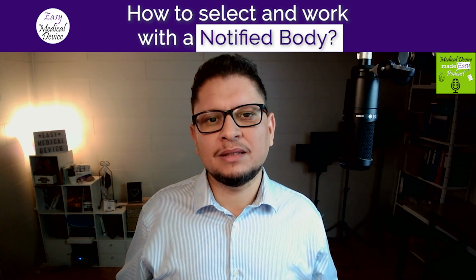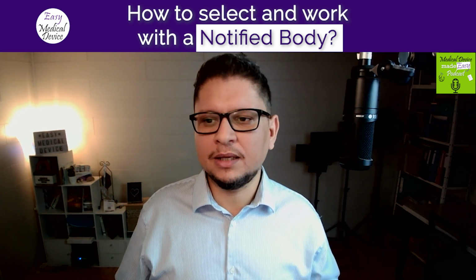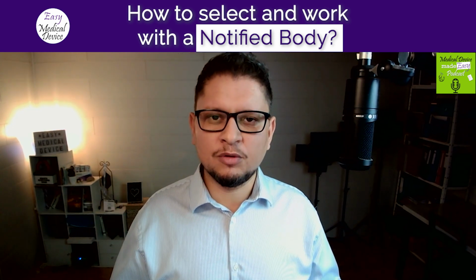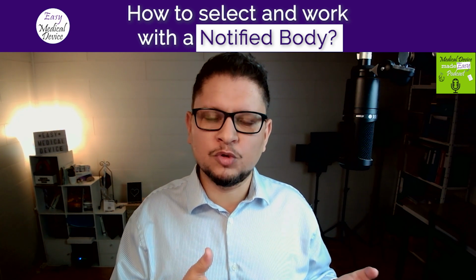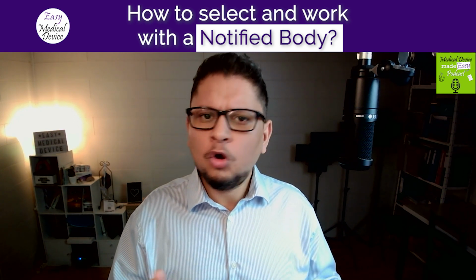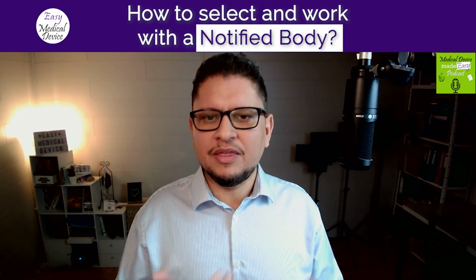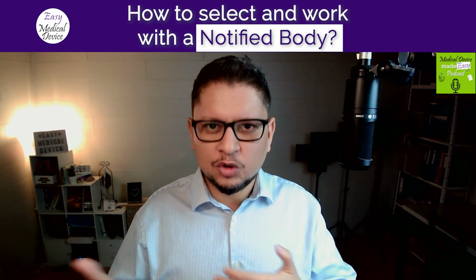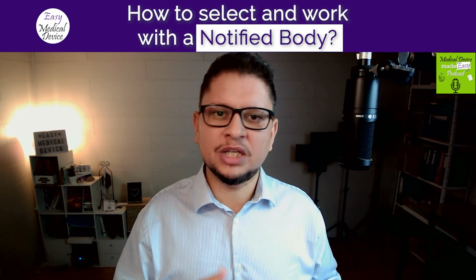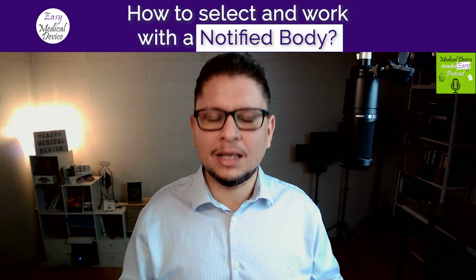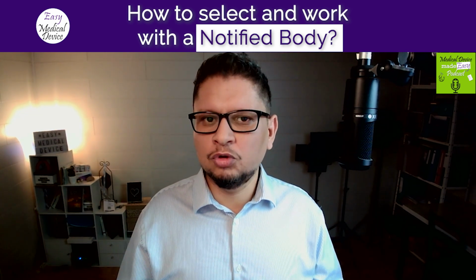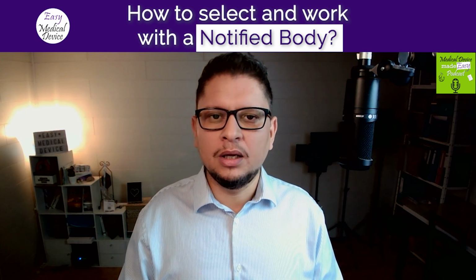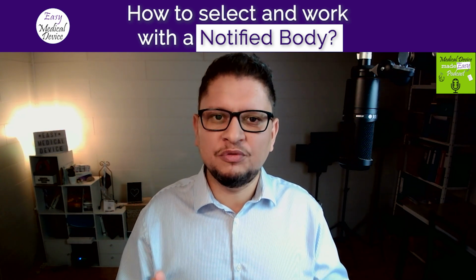But this is a mistake that maybe you are thinking of making: let's anticipate, let's get the ISO 13485 certificate without our products being on the market or manufactured, and after we get the ISO, we can start to manufacture. No, the audit will be checking all the ISO elements inside and proving that it's working. So don't go for a stage 2 or even a stage 1 audit if you haven't already manufactured a lot.